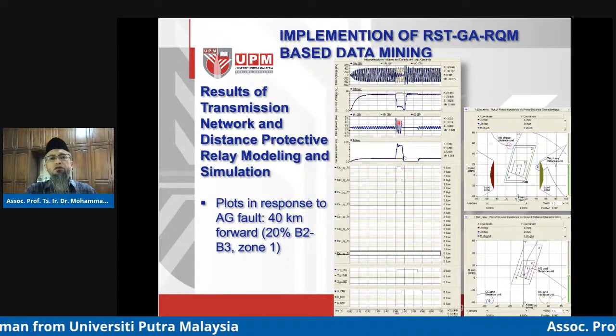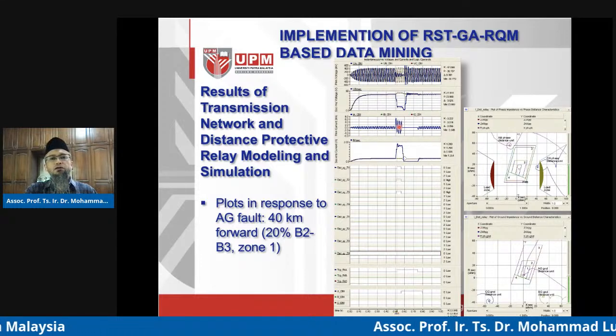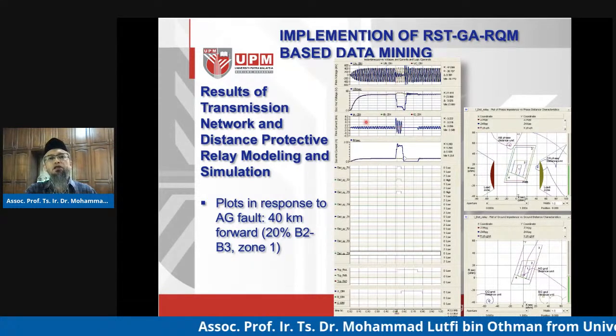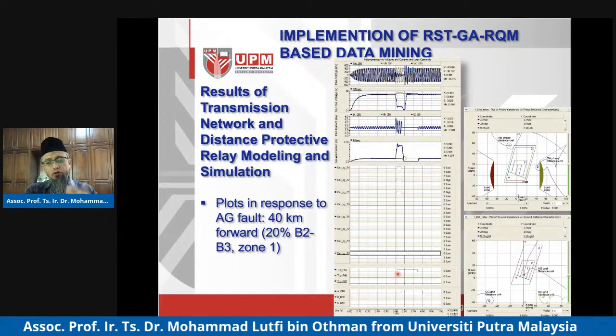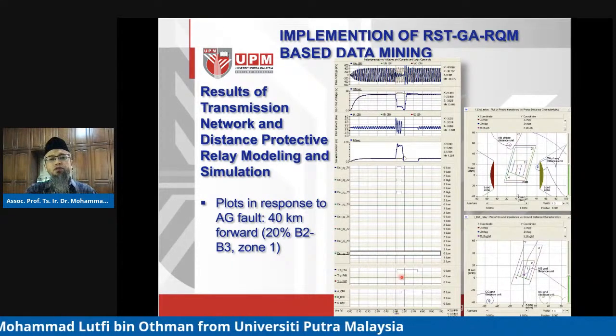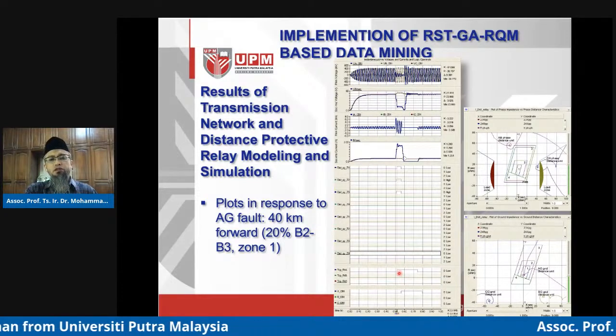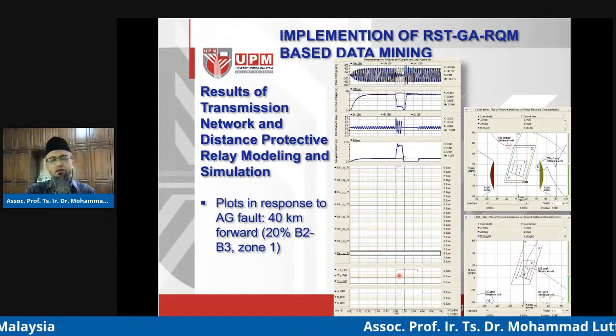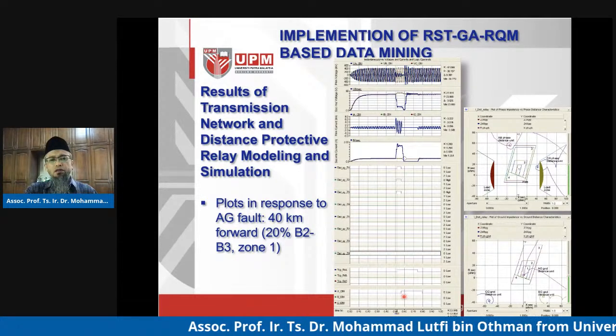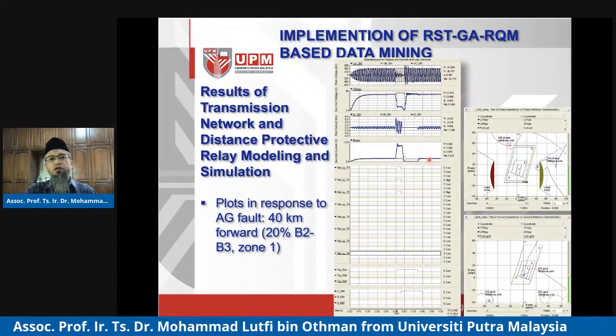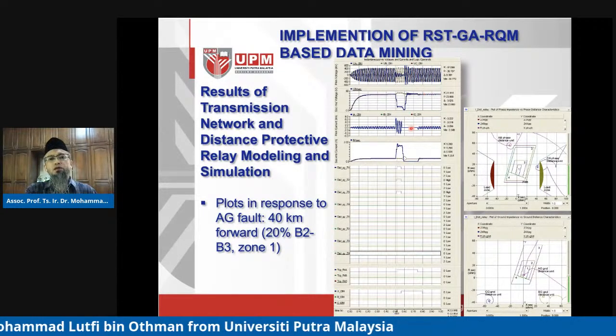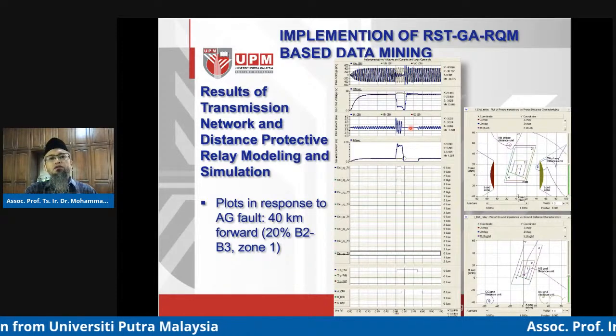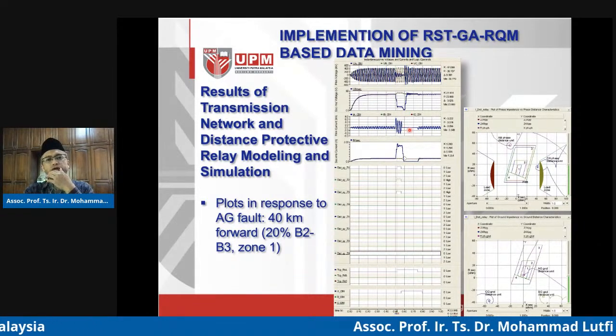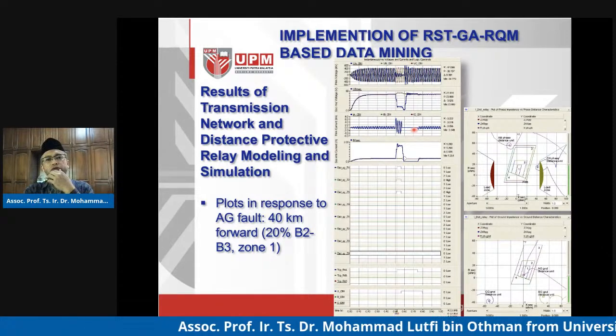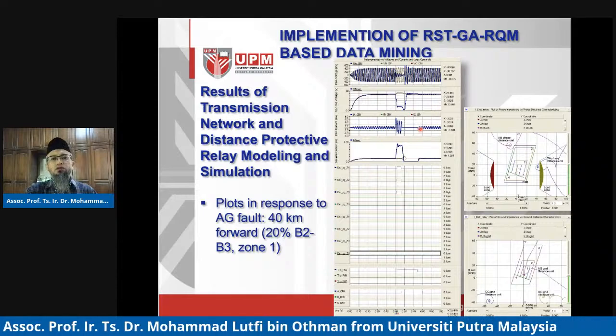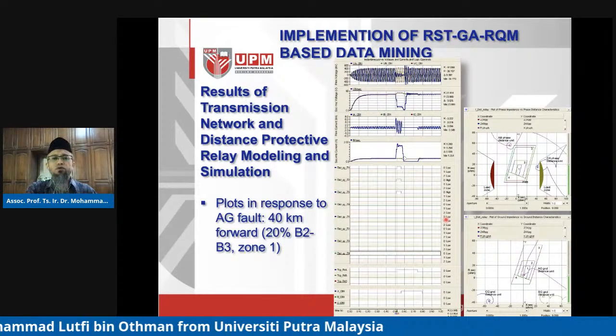So this is the fault, the surge in current that has been plotted here. We understand there is an A to ground fault, and because of that, the model relay has successfully asserted a tripping signal to the circuit breaker. Immediately, or rather with a little time delay after that, the circuit breaker trips the power system. That's why you can see the current is removed, because it has been disconnected. After a while, maybe because there's a recloser in place, the power system is reclosed back into the system. So this is operating as we really expected.